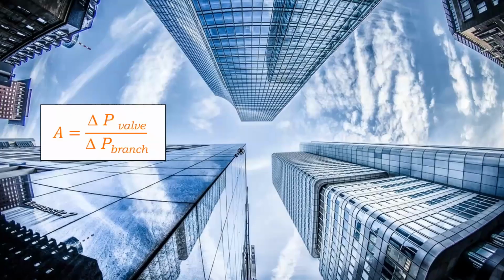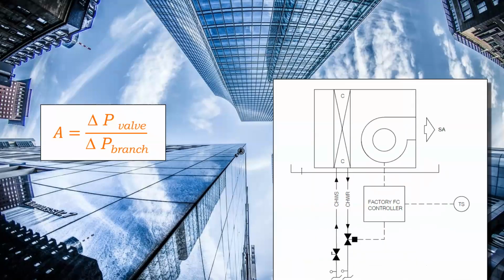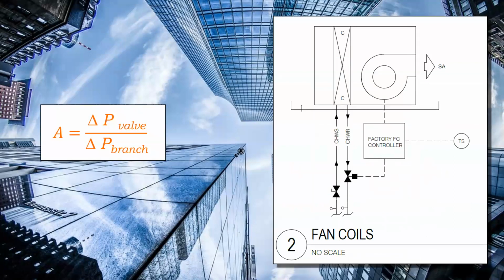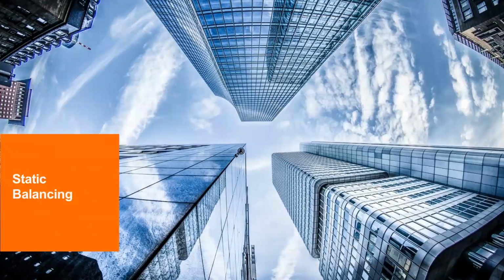Valve authority is simply how the valve relates to the branch schematic. It is the ratio of the differential pressure of the valve and the differential pressure of the branch. If we look at this diagram, the differential pressure across the valve is on either side of that valve, and the differential pressure of the branch encompasses everything on that branch. So what if instead of just that one fan coil, we have a series of 4 connected by a direct return piping system?